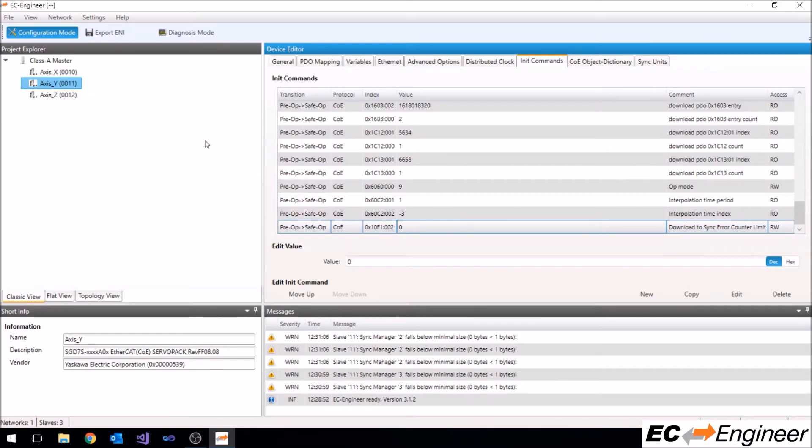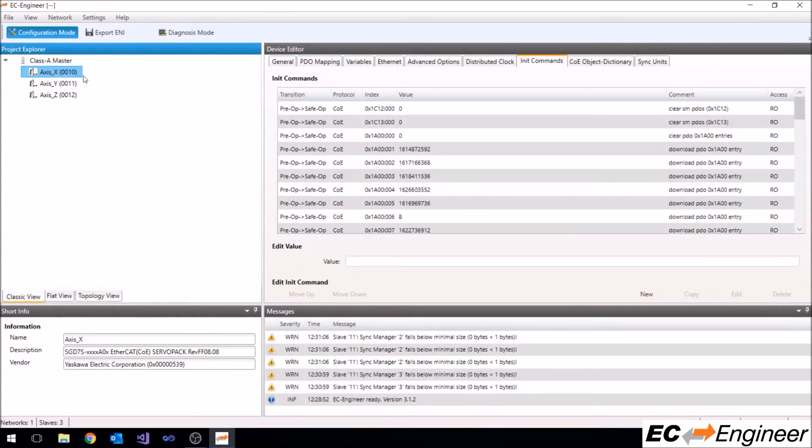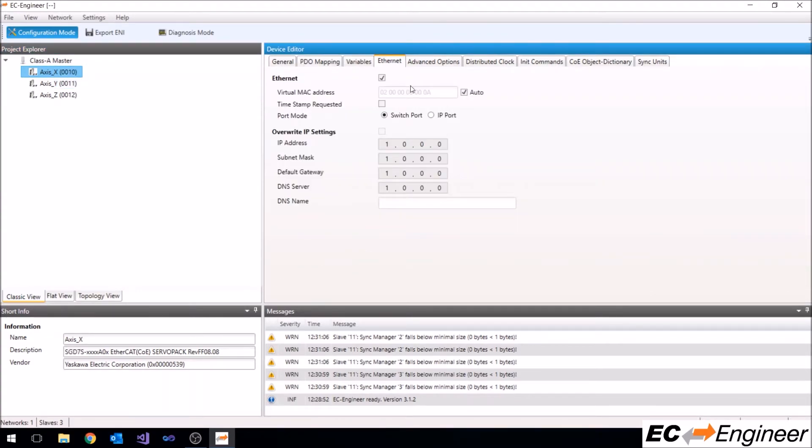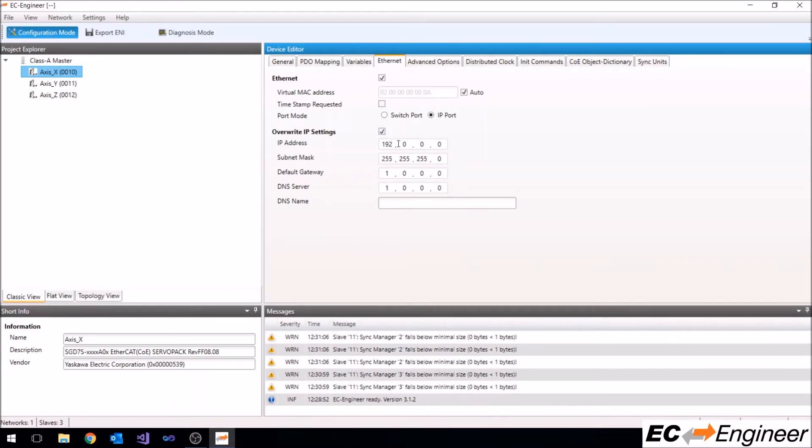Click on the slave device you want to edit in the project explorer area, select the Ethernet tab, check the box to overwrite the IP settings, and then type in the IP address information you desire. We will specify a unique address for each device in our configuration.